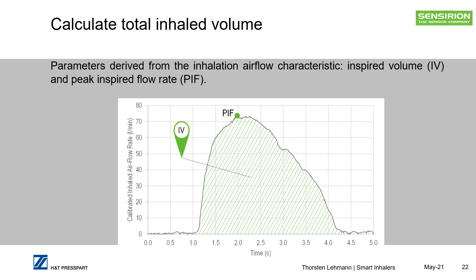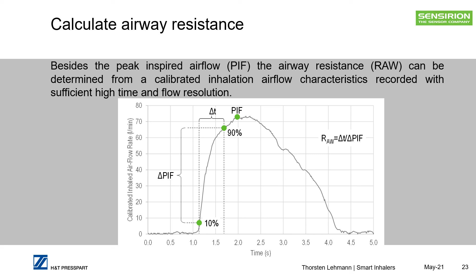Here, a calculation of the airway resistance is performed. The airway resistance is defined by the ratio of the time needed to increase the flow rate from 10 to 90% of the peak inspiratory flow rate, divided by the value of the set peak inspiratory flow rate. This gives us an indication of how severely restricted the airways are.